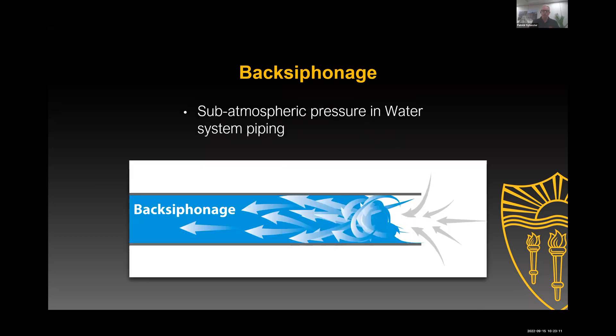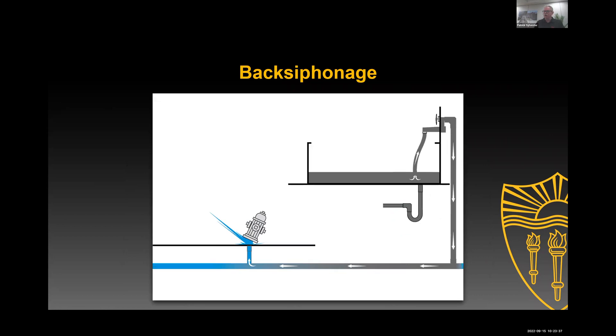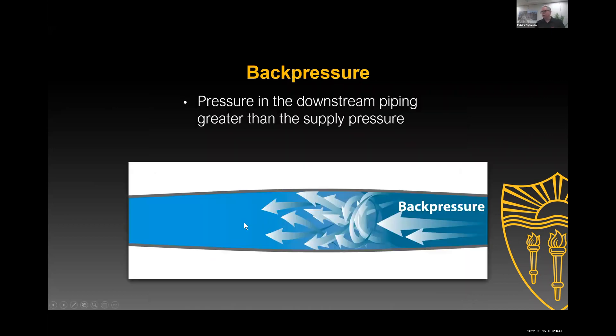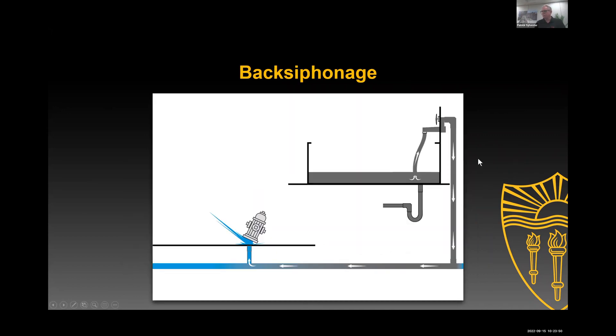There's back siphonage and back pressure. With back siphonage, water normally flows from left to right but is being sucked from right to left. That's defined as when we get sub-atmospheric pressure in the distribution piping — below 0 PSIG or below 14.7 PSI, below atmospheric pressure. Back siphonage occurs when we lose pressure in the distribution system, and as water pulls down, it creates a sub-atmospheric pressure, drawing flow backward.